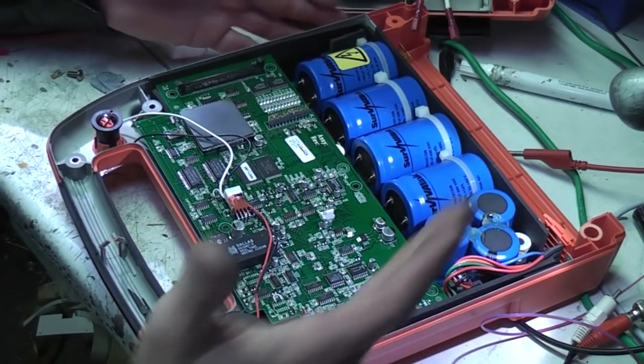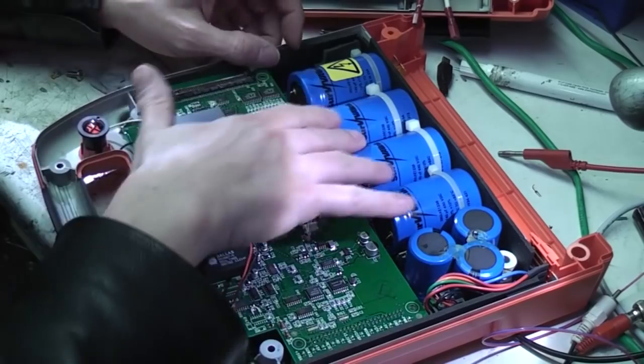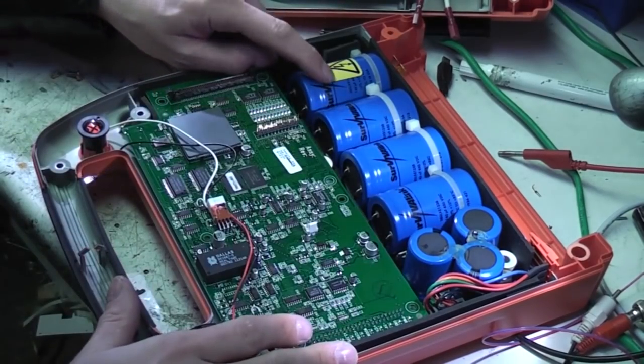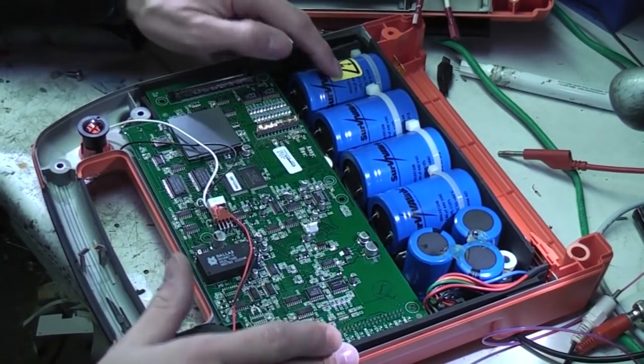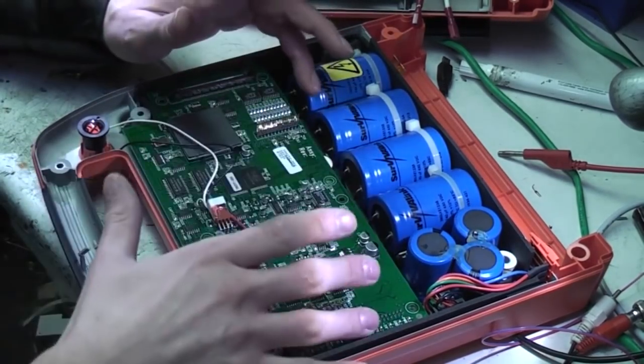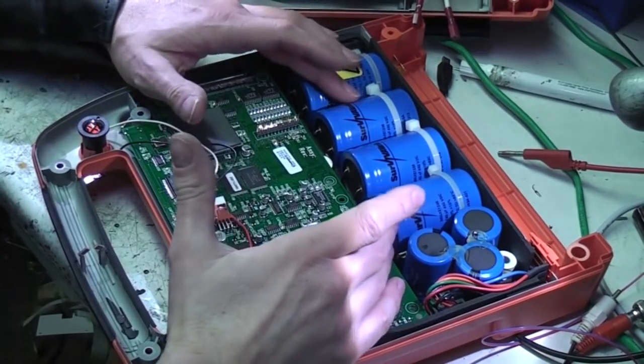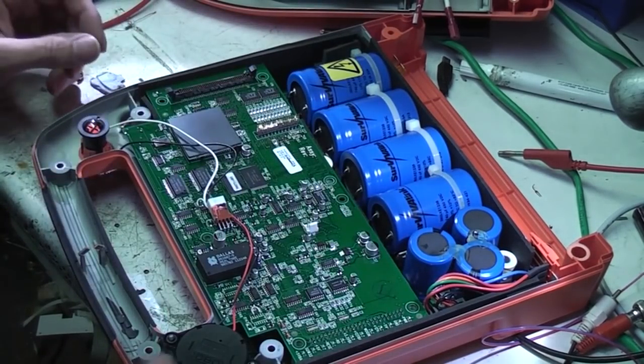But also a side effect, it means the defibrillator itself could be smaller. So what I'm guessing is these electrolytics, they're rated 740 microfarads at 450 volts. I'm guessing what they do is they probably use possibly series and parallel combinations to be able to get different voltages. Of course all the switching is now via semiconductors rather than mechanical relay type switches.